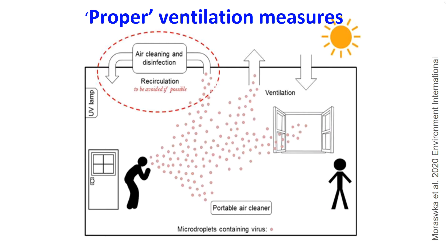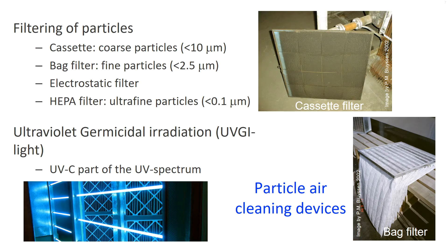If general ventilation seems not enough, or recirculation and reuse of air cannot be avoided, add air-cleaning devices. Air cleaning in most mechanical ventilation systems comprises filtering the outdoor incoming air of particles smaller than 10 microns by a cassette filter, and particles smaller than 2.5 microns by a bag filter.